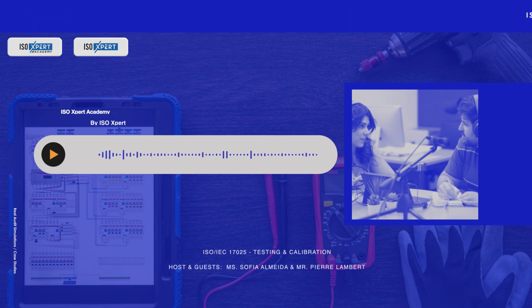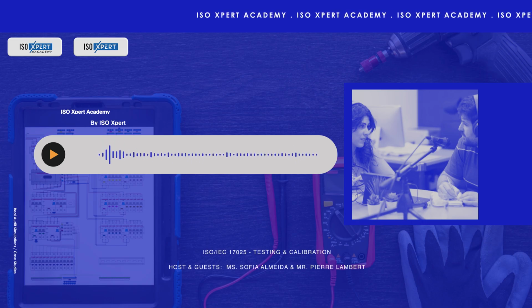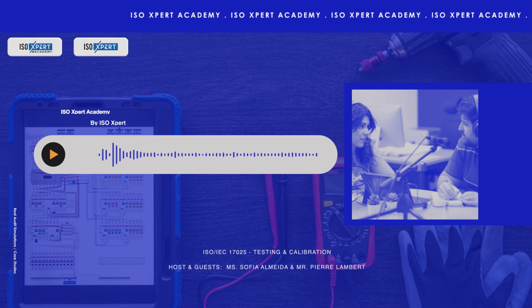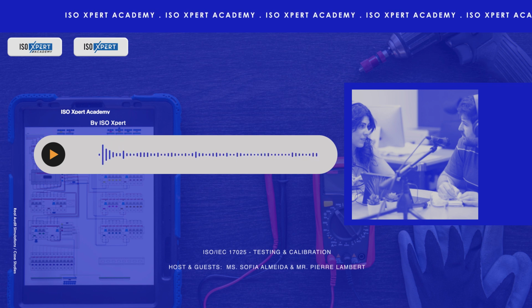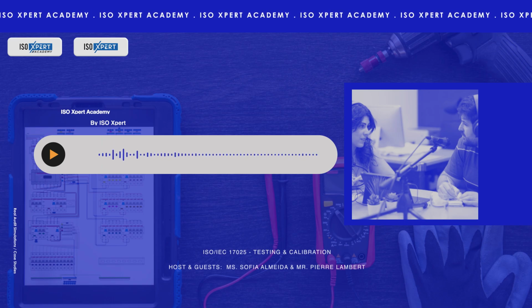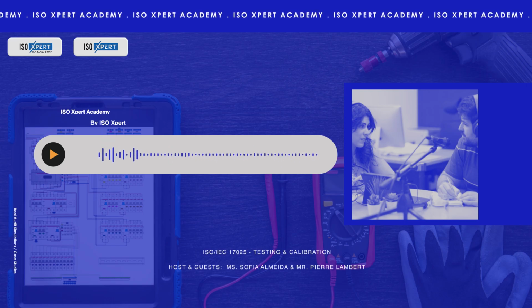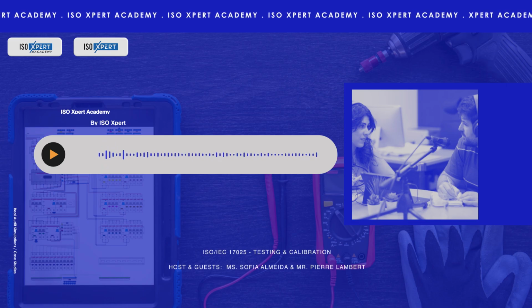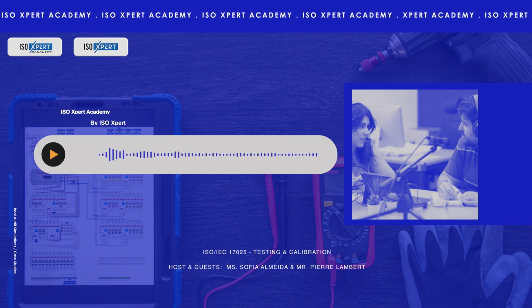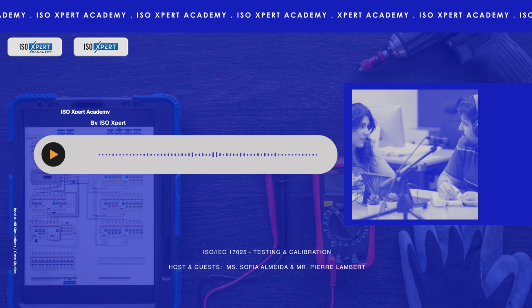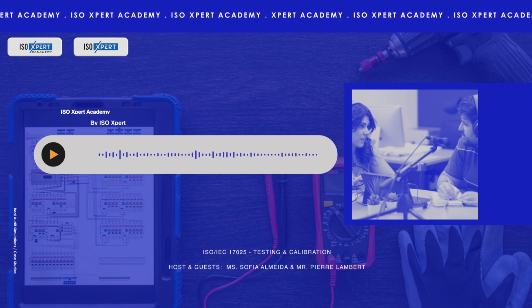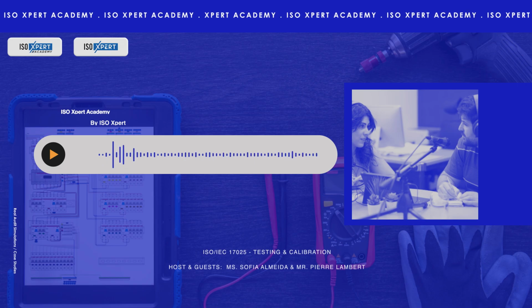Where did Perfect Calibration actually shine? What were their strengths, according to this audit? Yeah, absolutely. They showed strong compliance in several really fundamental areas, things you need for any decent quality system. Like what? Well, for instance, their management regularly conducts management reviews. That shows commitment right from the top. That's clause 8.9 for those following the standard. Okay, good sign. And they also consistently schedule and run their own internal audits, clause 8.8. So they're committed to checking themselves and improving. And what about the actual measurements, the core of what they do? This is huge. Their equipment calibration is traceable back to the Emirates Metrology Institute. That's their national standards body. Right, that's clause 6.5.